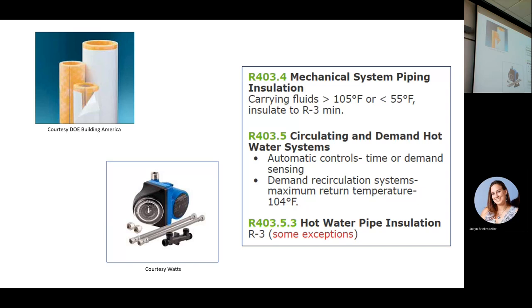Circulation loops. Do we see those very often? Someone builds a nice big home, they put a return line on it to the water heater, put a little pump on it with a little check valve and a timer on the pump so that during the day when you're going to be using hot water all the time, the pump circulates and keeps hot water close to all the fixtures, so you're not wasting a bunch of water and you have hot water fairly soon. Did you know that loop, that whole loop is supposed to be insulated?